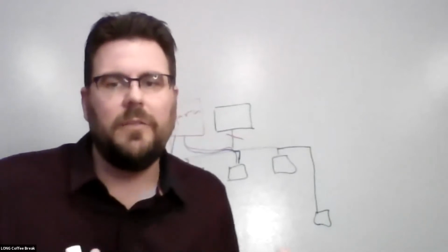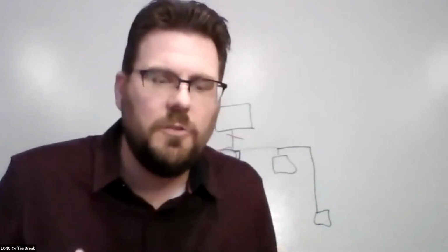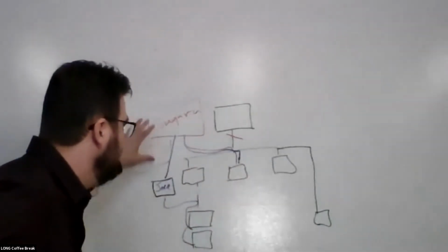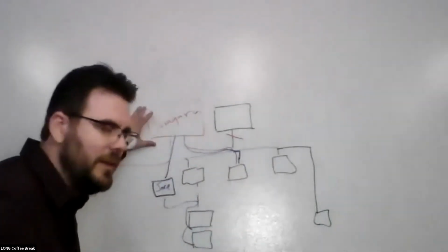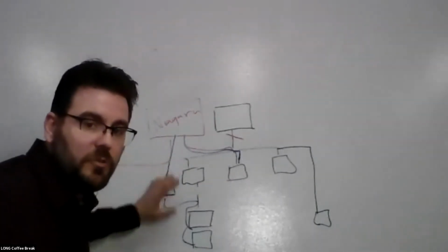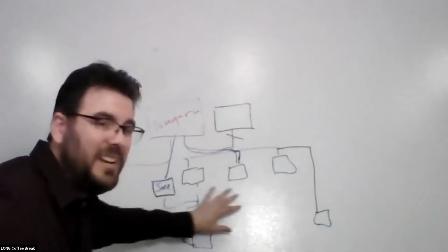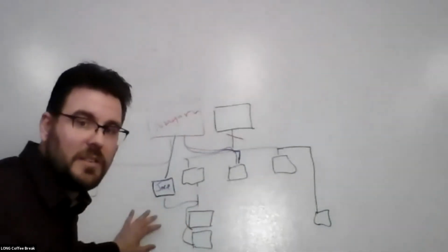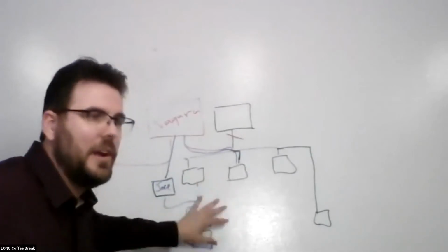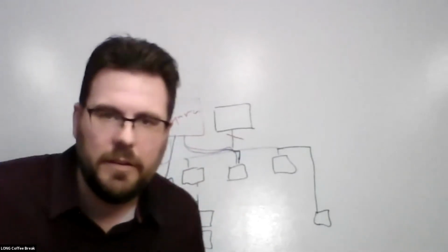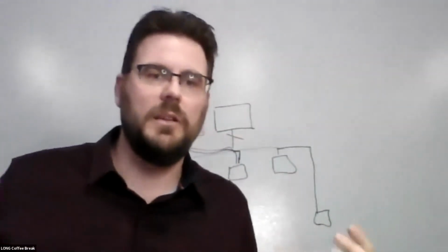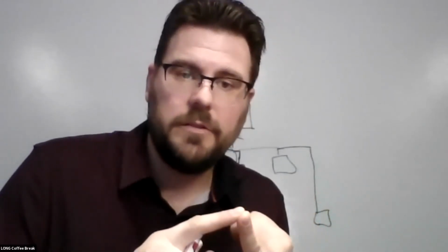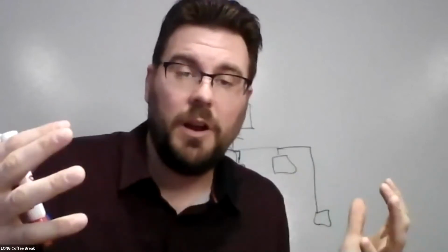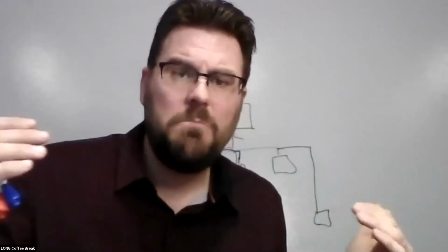So really what we want to do is just make sure we help educate on the different levels, right? You've got your head end, your server level, you've got your equipment level controllers, and then you've got your field level controllers. Depending on the system, whether it's Siemens, Johnson Controls, Alerton, whatever it might be, there are paths to move out of that particular situation toward an open system where you have multiple service providers that can service that type of product, and you're not locked in, and then you're upgrading technology and can mix and match technology.